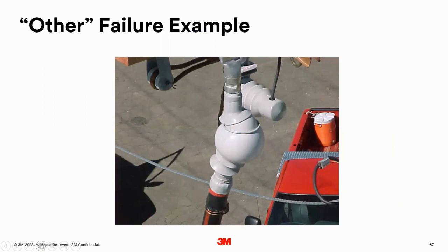This one here, and I'll get into reasons why this happened. This is a QT2 splice that ended up having water in the cable's strands. So what happens is aluminum oxide on the conductor strands combined with water created hydrogen gas. This gas will either burst rapidly and explode, but more often than not, it burps down the interface between the cable and the termination. And this is what you see, just like a big ball of air in there.